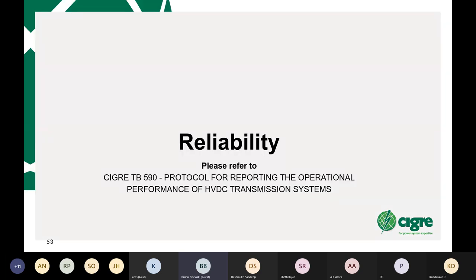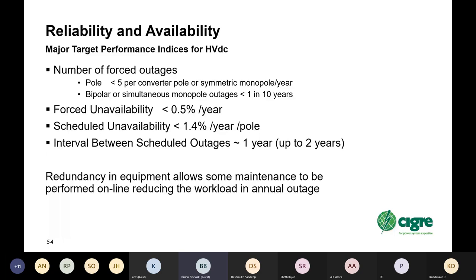Reliability, and for reliability, there's a very good CIGRE brochure, TB 590, protocol for reporting the operational performance of HVDC transmission systems. So what are typical reliability and availability indices for HVDC systems? Typical numbers are number of forced outages, less than 5 per converter pole or symmetric monopole per year. For bipolar or simultaneous monopolar outages, less than 1 in 10 years. Forced energy unavailability, less than 0.5% a year. Scheduled unavailability, less than 1.4% per year. That equates to about a week per pole.